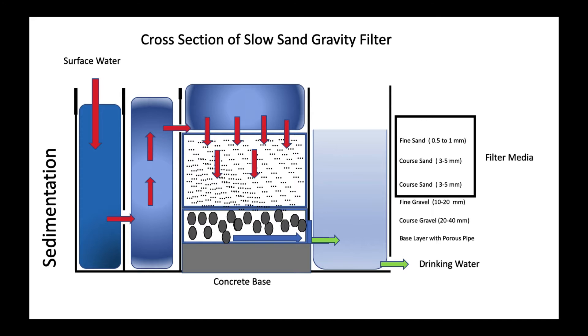This is a schematic diagram of a slow sand filter showing inflow of water and outflow of drinking water. It is made up of various layers known as filtering media. From the base upward, the size of the filtering medium decreases. At the basement there is a porous pipe with laterals, covered by coarse gravels, followed by fine gravels, followed by sand with decreasing particle size.